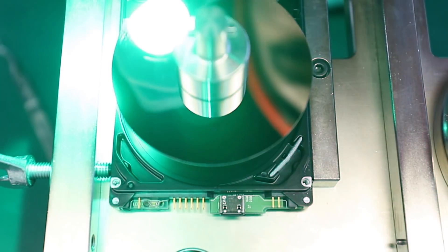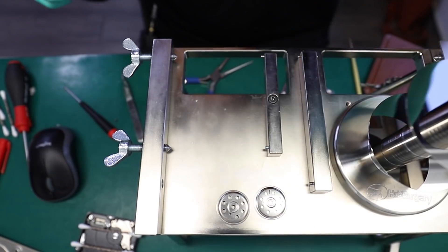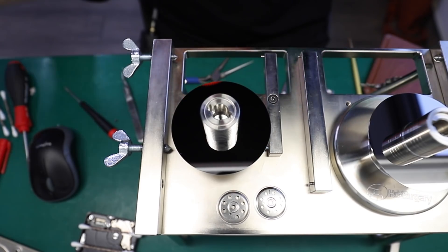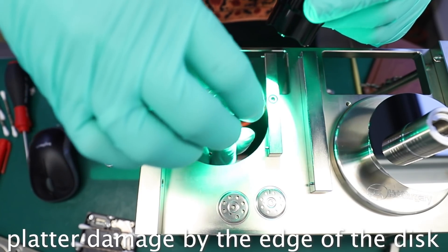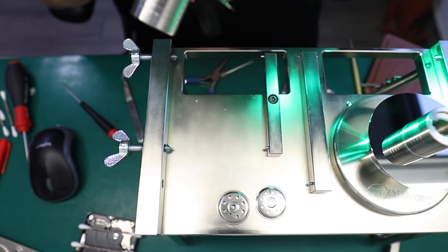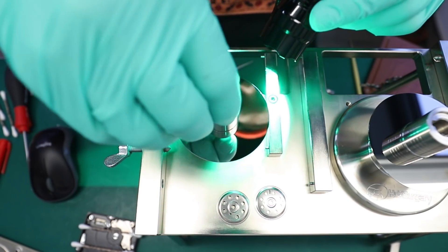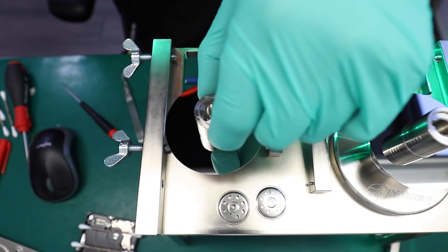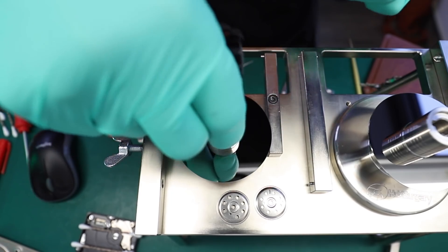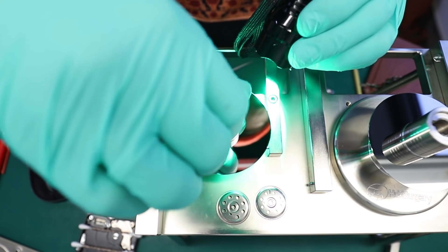What isn't normal is the cloudiness you see appearing on the surface of the disc right now. That's unusual. I was very surprised to see that on the bottom disc. We often see stuff like this on the top disc when somebody put a fingerprint on their drive and then watched the drive spin for some time, and all of that contamination gets picked up and smeared around the disc. Or somebody put a fingerprint on their disc and then pulled out a kleenex to wipe it off, and it just makes all hell break loose. In our situation it's the lower disc. Technically there is no easy way to access it, but nonetheless we're dealing with the aftermath here.